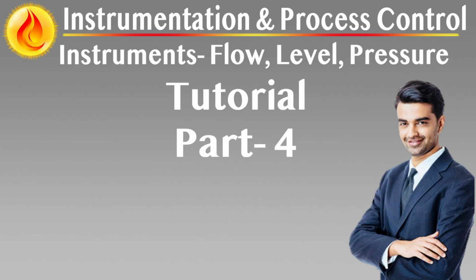Pressure drop through PD meters is generally higher than that of turbine or Coriolis meters, especially in high viscosity or cold fluids. Oversizing the line, preheating, or using pressure-reducing bypasses may be required in such cases. Installation requirements and mechanical protection. PD meters must be installed with flange connections, level and properly supported. Piping must exert no strain on the meter body.